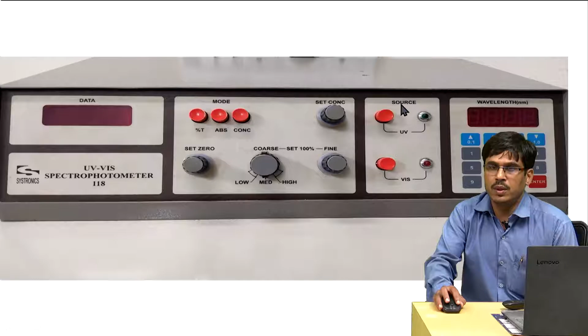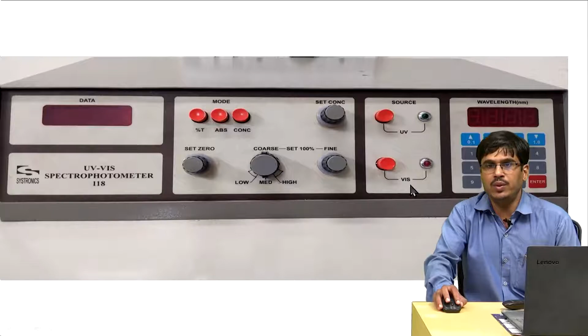Here again, to select a proper source, 2 push buttons are given on the control panel. One is the UV push button that selects the UV light source, and another is the visible push button that selects the visible light source. On the right there is a panel. By using this we can manually enter the wavelength of the desired measurement. In other words, by this panel we can give the desired wavelength to the instrument.